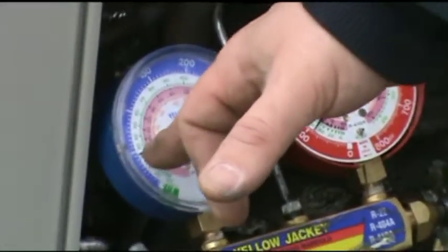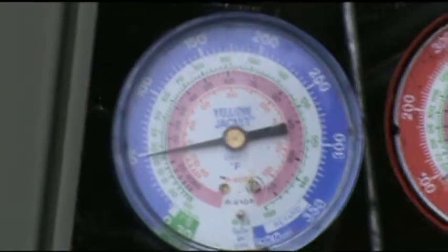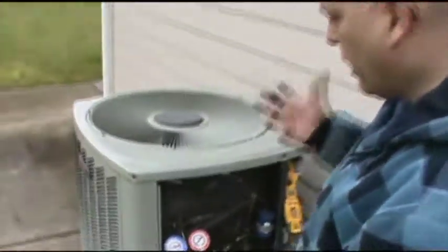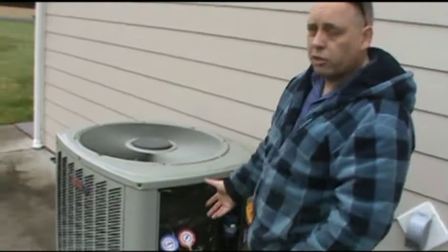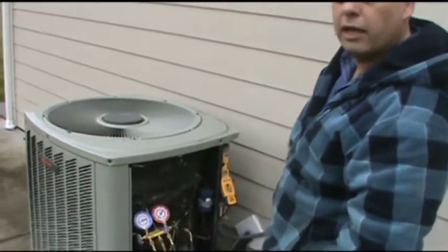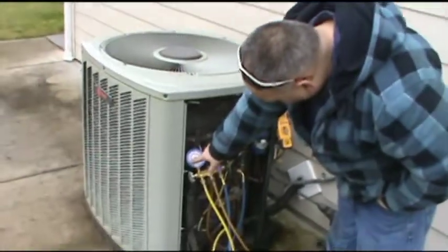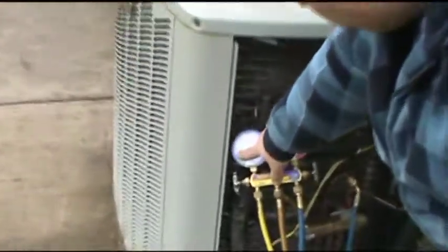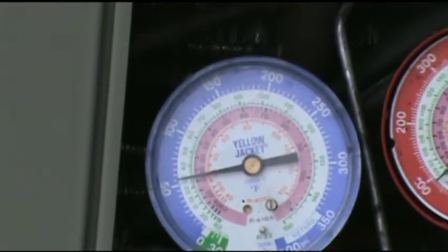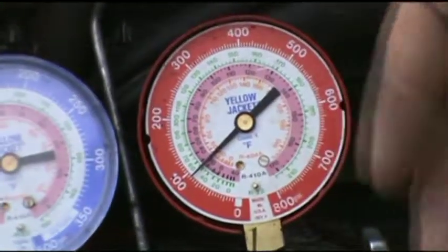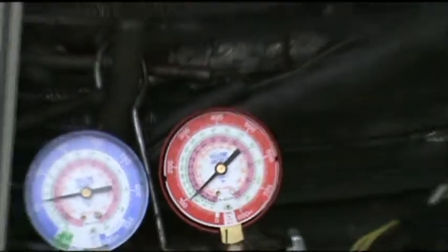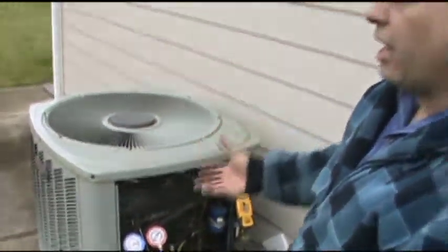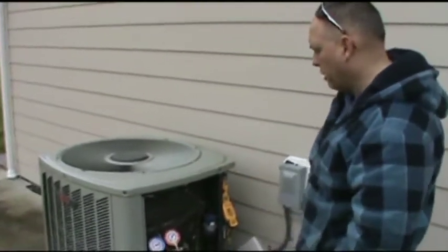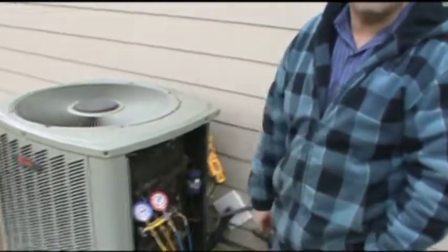Typically, we want to see our suction pressure at 60 psi or higher, and we want to see our high side pressure approximately 100 psi or more above that. Now, we're not going to get those numbers today because of the temperature, but I can get a good idea of how well it's running by the pressures that I do see and the temperature I'm going to see inside coming out of the ductwork. So I have a suction pressure of 55, which is really close to the 60 I want to see. My high side pressure is very low, approximately 100, which is much lower than I would expect in a normal operating condition. But again, that's because it's 46 degrees outside. It's still wintertime. So this is the kind of pressure I would expect to see in a wintertime check.